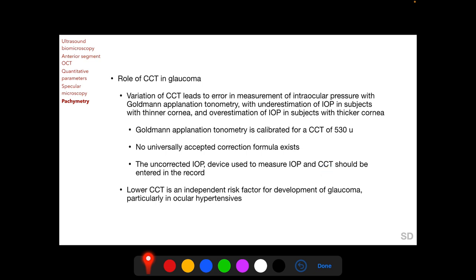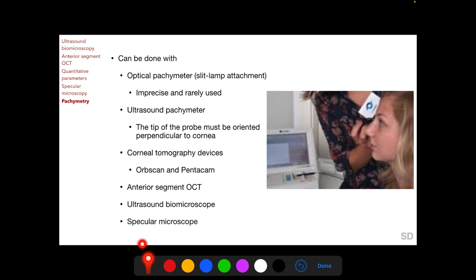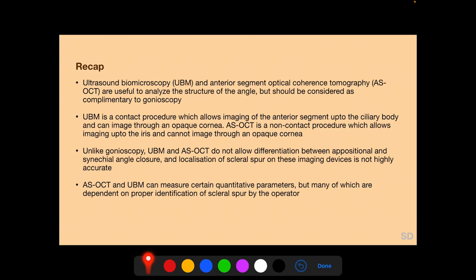Pachymetry can be performed with various devices. Optical pachymetry, formerly available as a slit-lamp attachment, was found to be imprecise and is rarely used today. Ultrasound pachymetry is a commonly used device; during measurement the probe tip must be oriented perpendicular to the cornea. CCT can also be measured with corneal tomography devices such as the Orbscan and Pentacam, and with the devices discussed in this session: AS-OCT, ultrasound biomicroscope, and specular microscope.